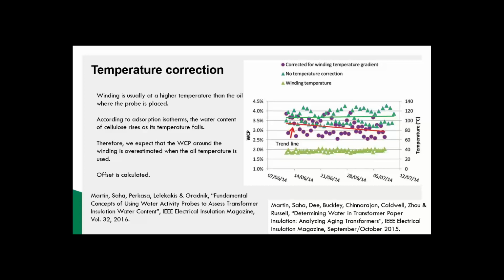Now, in terms of the degree of difference it can make, it does just depend on how the transformer is being run. If the transformer is being run at a higher load, then we might expect to see a higher gradient of temperature between the oil and the winding, which then just means we have more of an uncertainty in the water content of paper measurements. This graph here just shows an example of it. So we've maybe 0.5% less when the algorithm is applied.